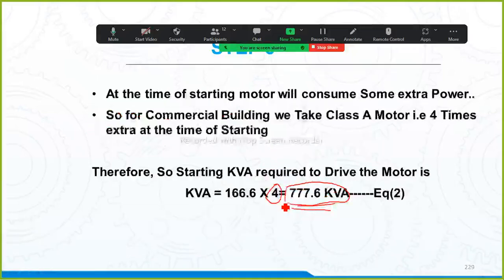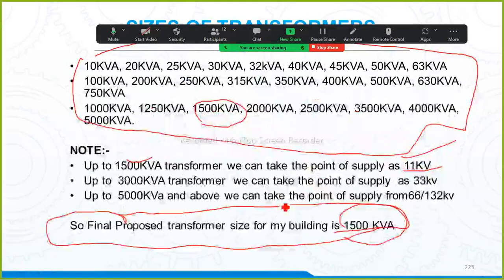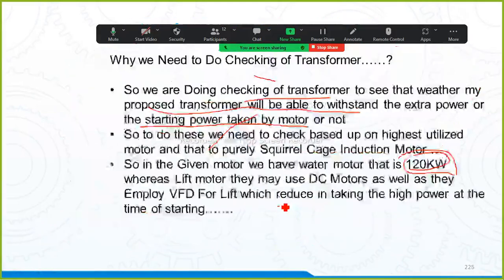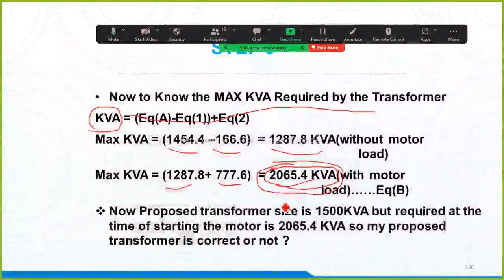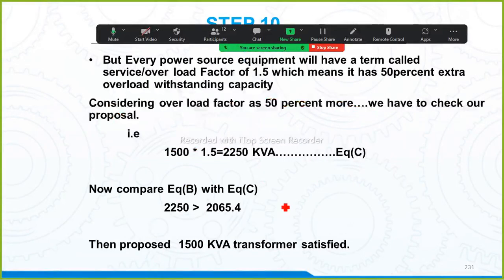But what had you proposed as the transformer? You proposed a transformer of something like 1500 kVA, but your requirement is 2065.4 kVA. So the proposed transformer size is 1500 kVA, but required at the time of starting the motor is 2065.4 kVA. So is my proposed transformer correct or not? First, I need to know whether it's correct or not.